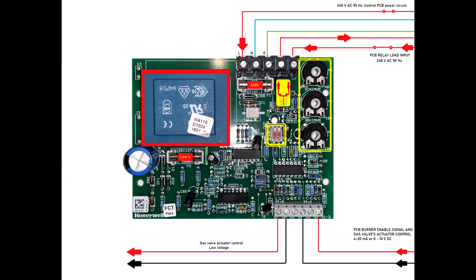and to enable the burner. If you make a mistake, as an example, to allow this relay to be closed when you apply less than 1 volt, then on some occasions the outdoor humidity or any little tiny electrical leak through these semiconductors could enable that relay, and the burner can be activated without this printed circuit board getting an instruction to run the burner. So you really have to pay a lot of attention to these potentiometers.